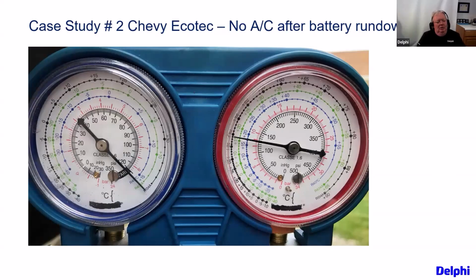Now this is on a hot engine - let me rephrase that, because what would make it 120? If it was full static and you just put gauges on it and it hadn't been started, the temperature of the refrigerant would be room temperature, agreed? As long as the refrigerant doesn't leak out into a lower pressure environment like the atmosphere.